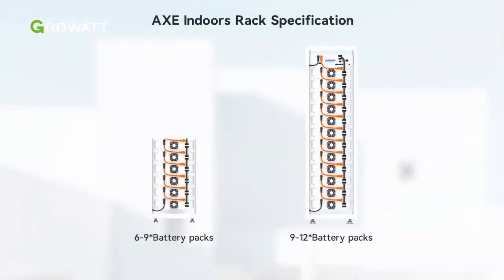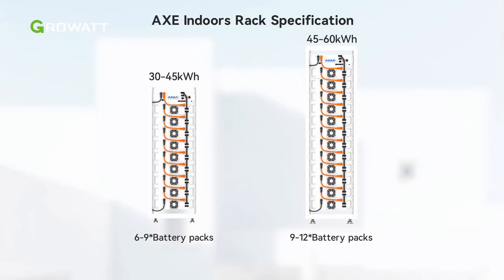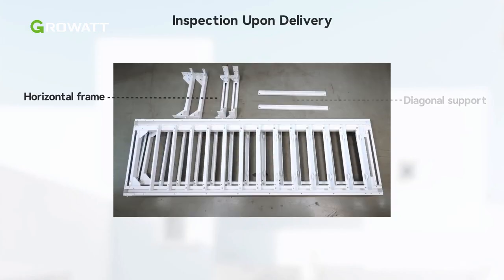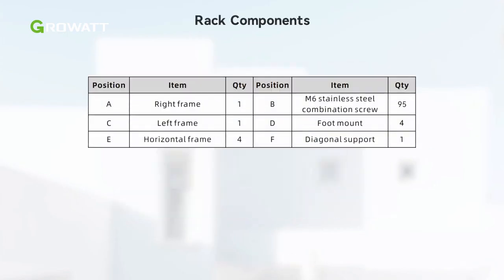Depending on the size of the battery system capacity you choose, we offer 2 different sizes of battery racks. They can carry battery modules up to 9, 45 kWh, or 12, 60 kWh. In this video, we use a high rack as an example. After unpacking an AXE battery system, check if the scope of delivery is intact and complete. Refer to this table in the manual and check the following items.